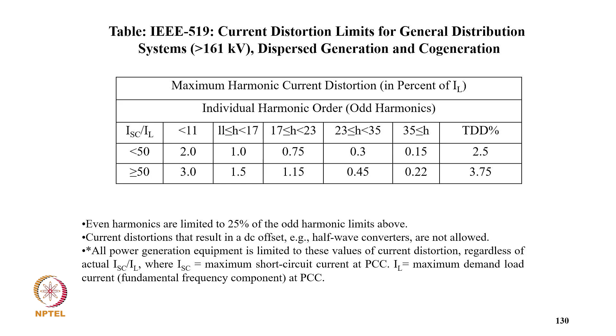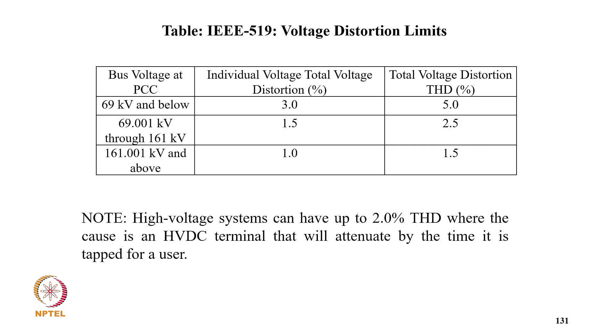Then the voltage distortion limit, of course, has a tighter limit. If it is 69 kV and below, the total harmonic distortion limit is 5% and individual harmonics not more than 3%. For 69 to 161 kV, individual harmonics are 1.5% and total harmonic distortion 2.5%. Above 161 kV, individual harmonics are 1% and total harmonic distortion not more than 1.5%. High voltage systems can be up to 2% THD where the cause is an HVDC terminal, which will attenuate by the time it is tapped for the user.